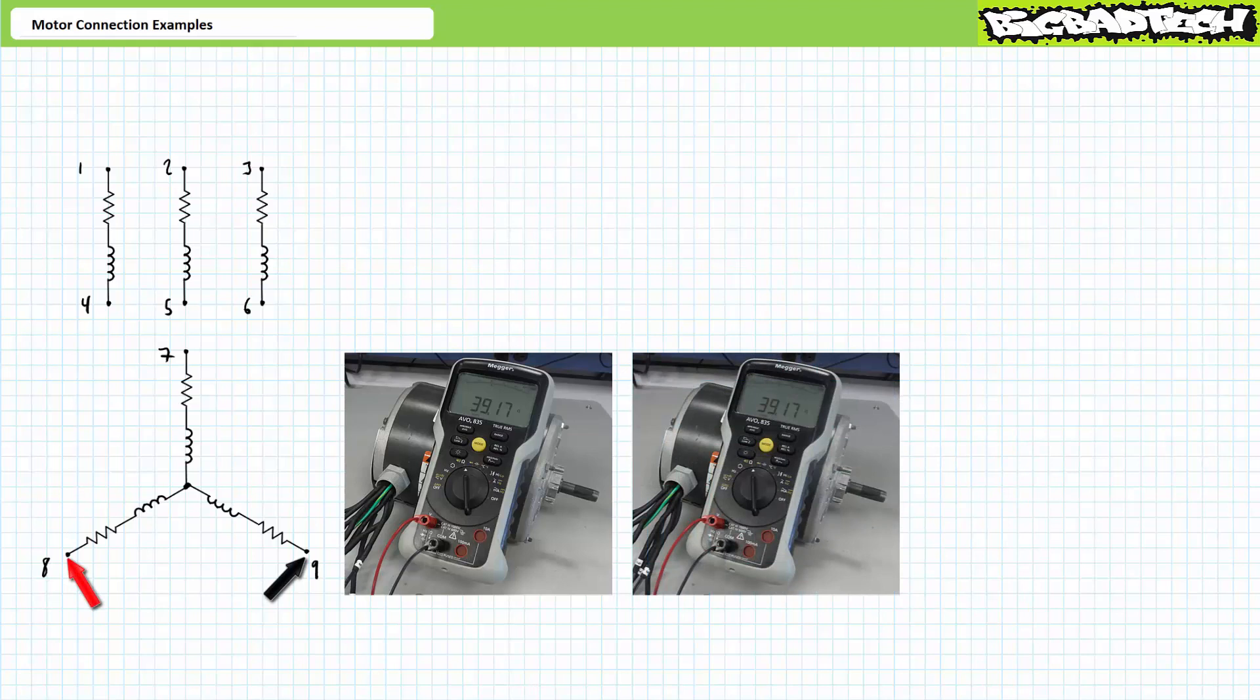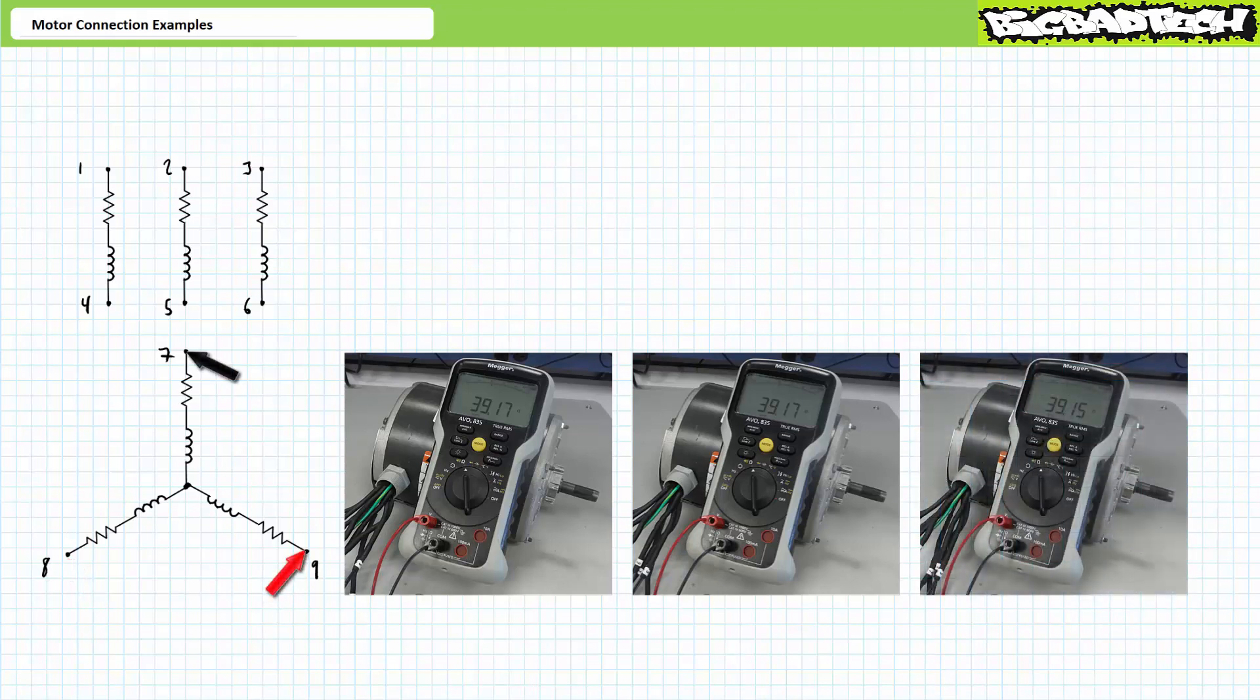Similarly, an ohmmeter between terminals eight and nine sees winding eight and nine in series. As previously, the ohmmeter sees a resistance of roughly 40 ohms which is consistent with a series combination of two identical 20 ohm windings. Finally, an ohmmeter between terminals nine and seven sees winding nine and seven in series. The ohmmeter sees a resistance of roughly 40 ohms which is again consistent with a series combination of two identical 20 ohm windings.